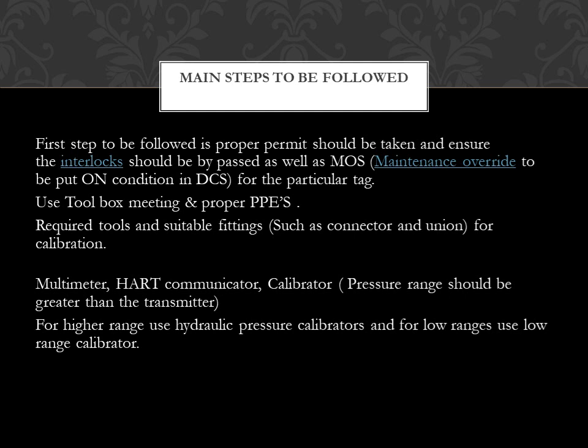Required tools are suitable fittings such as connector and union for calibration, multimeter, HART communicator, and calibrator. Pressure range should be greater than the transmitter. For higher range, use hydraulic pressure calibrator, and for low range, use low range calibrator.